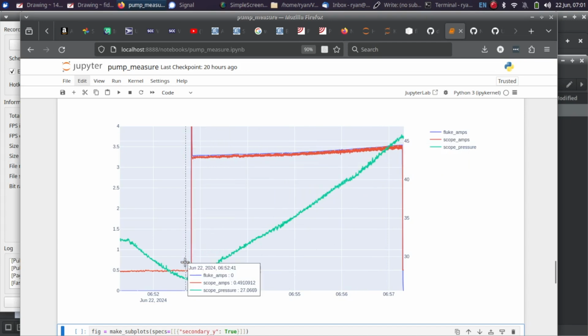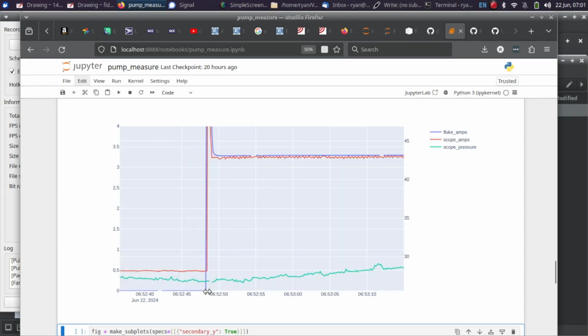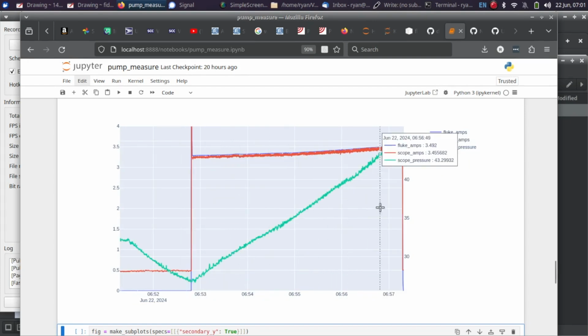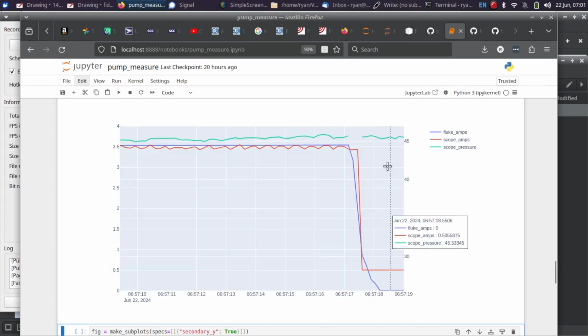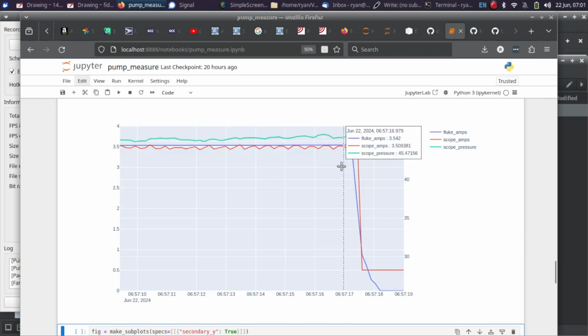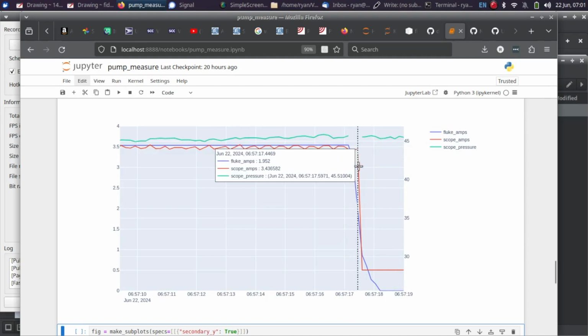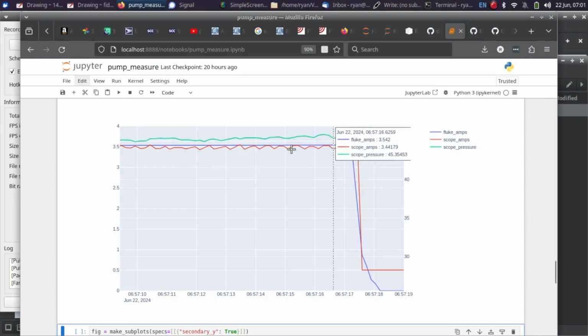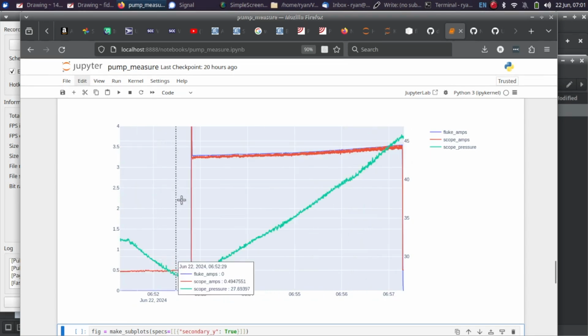So it looks like our cut-in is around 27 psi, and our cut-out is around 46 - interesting that we lost pressure data here. Cut-out around 45.5. So both of those are a little higher than expected. I was expecting it to be set to a cut-in closer to 20 and a cut-out closer to 40. So that's one takeaway already.